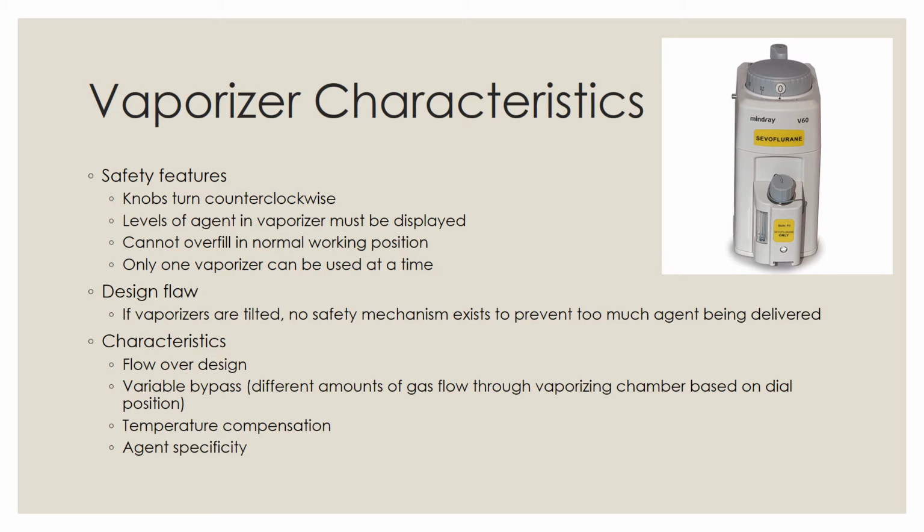They're variable bypass. This means that different amounts of gas flow through the vaporizing chamber based on the dial position. So some will flow through the vaporizing chamber and some will flow through the bypass chamber and then meet at the exit of the vaporizer.